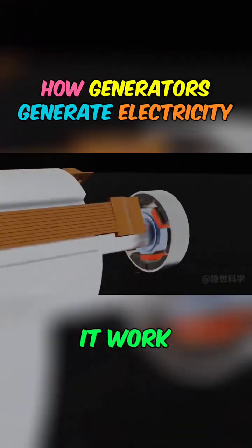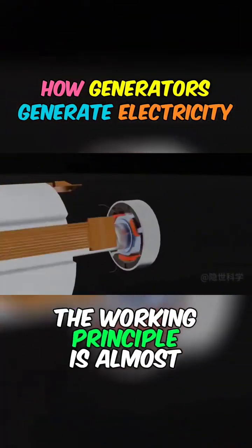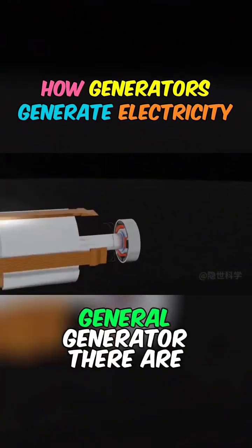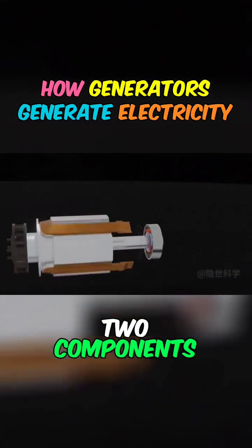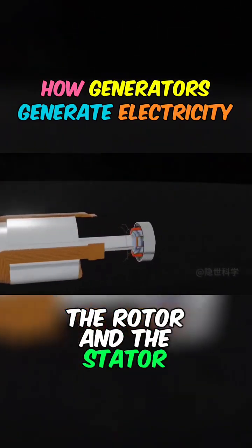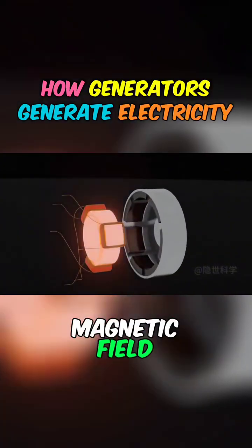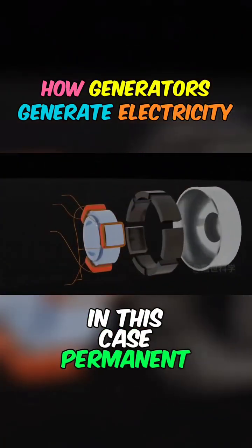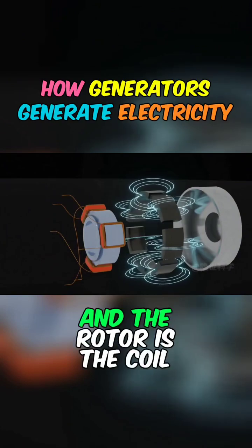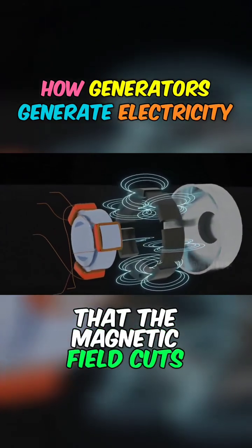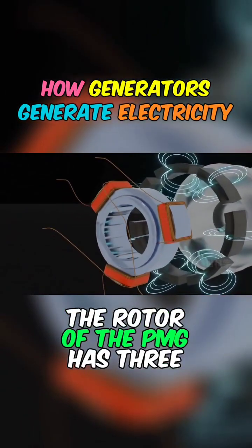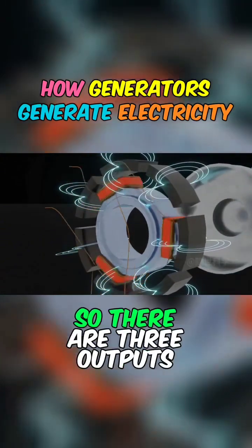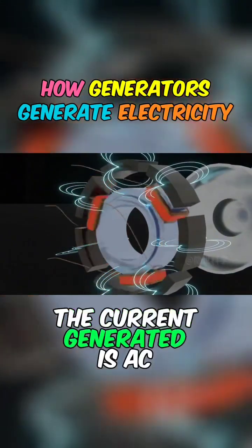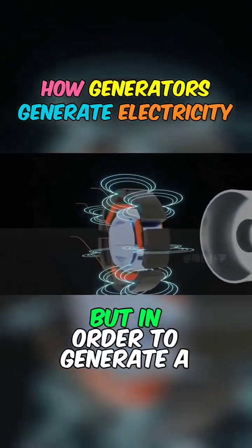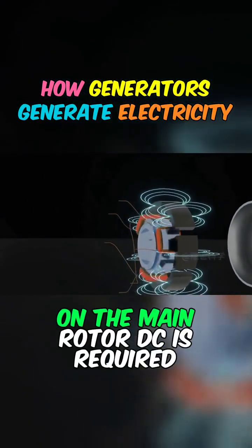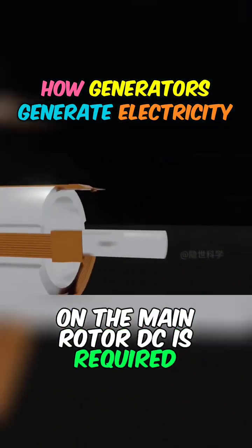So, how does it work? The working principle is almost the same as a general generator. There are two components, the rotor and the stator. The stator provides the magnetic field. In this case, permanent magnets are used, and the rotor is the coil that the magnetic field cuts. The rotor of the PMG has three coils, so there are three outputs. The current generated is AC, but in order to generate a magnetic field on the main rotor, DC is required.